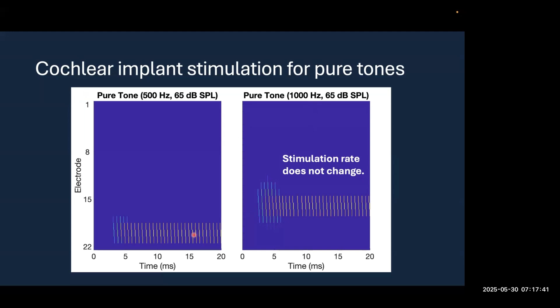So the most commonly used way of stimulating a cochlear implant just uses a fixed rate stimulation, often 900 pulses per second. So if you play a 500 hertz tone, the implant stimulates at 900 hertz. If you play a 1000 hertz tone, the implant stimulates at 900 hertz. And so it's not using that timing information. There are exceptions, and in particular, Med-El Corporation has a fine structure processing algorithm that is trying to put that timing information back in. But still today, the most common conventional way of stimulating completely discards that timing information.